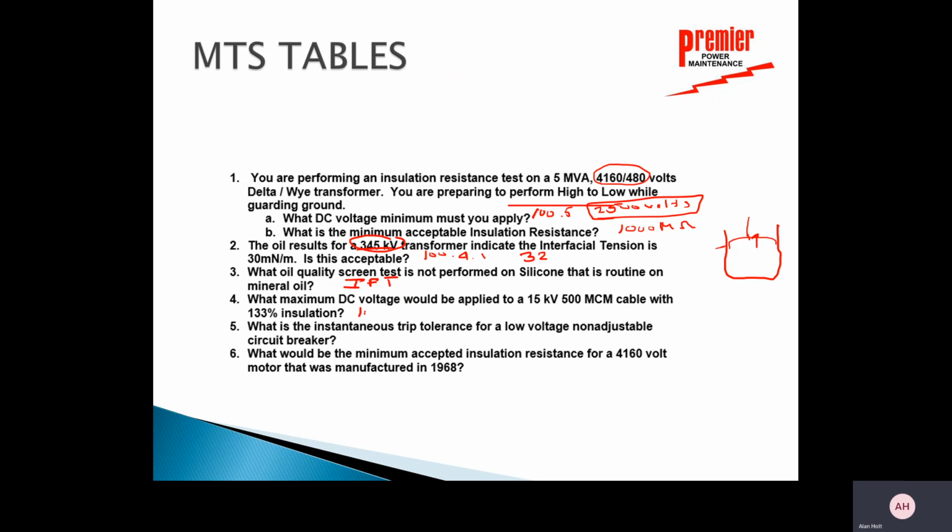Well, that's a table that I really hated. It's 100.6.1. And it's one that I looked at in the parking lot before I went in and took the test, because it gives us different values for different size cables, different voltage cables, and different percent insulation. And they expect you to know some of those sometimes. I had a couple questions in a couple of my exams. But the bottom line here is for that situation, it's 20 kV.